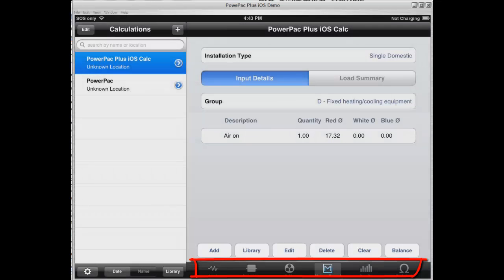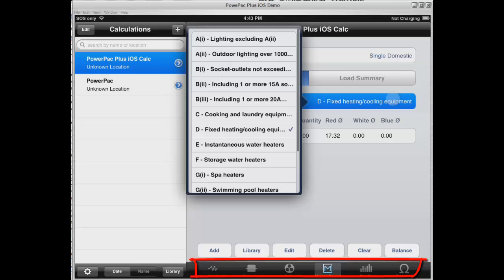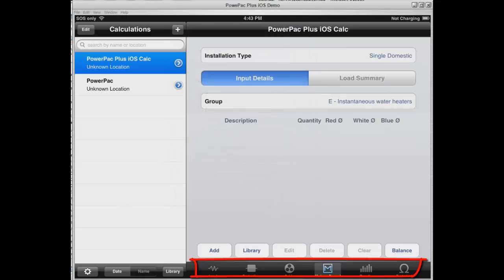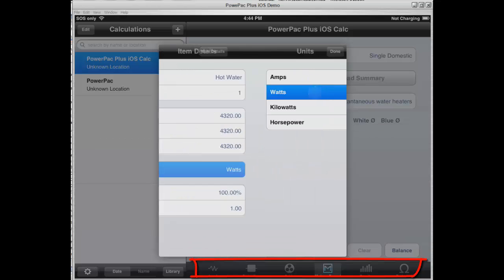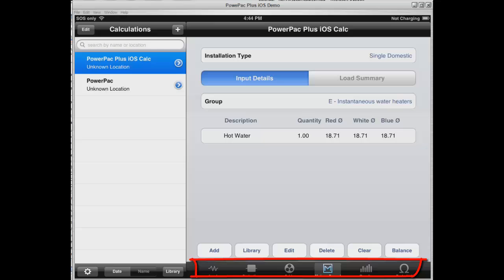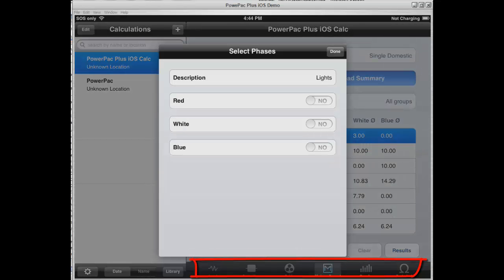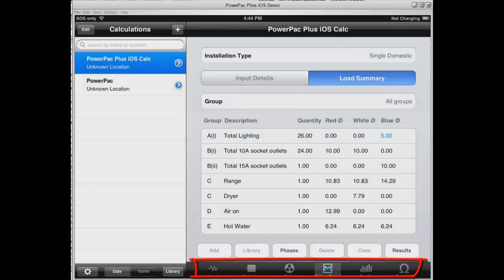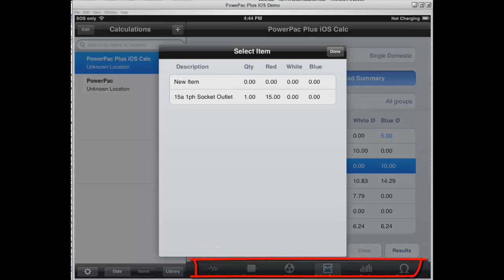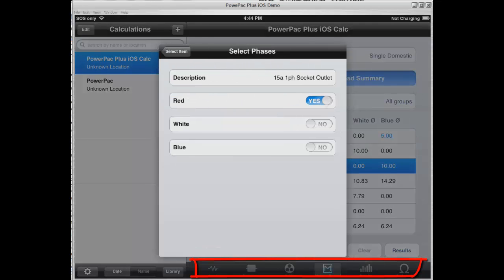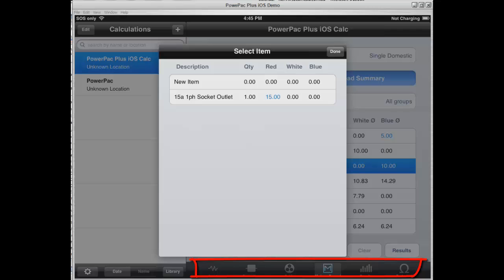Once finished, click Done. We're going to add our instantaneous hot water system and add that manually. For all users of PowerPac, you can build a library of commonly used items for the type of work that you do. Once we've done this, we're going to hit the balance button to look at the results. We're now balancing the lighting and the 15 amp outlets by nominating the phases that they're on, same as the standards.